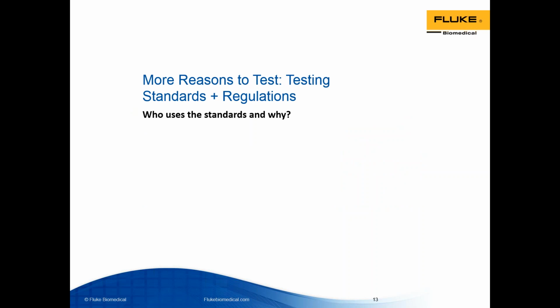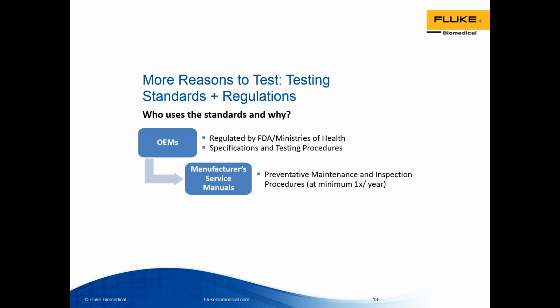So who uses the standards, or should use the standards, and why? Well, first, OEMs. The FDA and ministries of health regulate the medical device manufacturing, the sale, and ongoing safety review within a country. They'll also approve incubator designs that can be sold in the USA or specific countries based on the data collected when following the prescribed tests in the IEC standards for incubators. Thus, many, if not most, manufacturers base their specifications and their testing procedures around the standards, and from them stems the manufacturer's service manual.